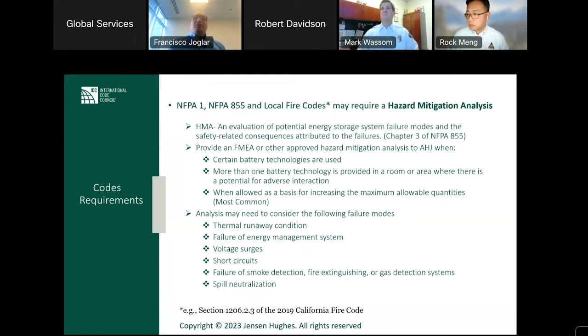What if your energy management system, your battery management system fails? What are you going to do in those cases? If there are voltage surges in the system itself, that is not necessarily a failure mode of the battery, same as short circuits. What if your mitigation systems, instead of fire, smoke detection, gas detection, all of that fails, and dealing with spills? All of this does not necessarily refer to the battery. These are not failure modes of the battery. They are failure modes either of the battery, the system, or the system that you have in place in that location to deal with these events. And that's why I tend to think that this is a little bit confusing.